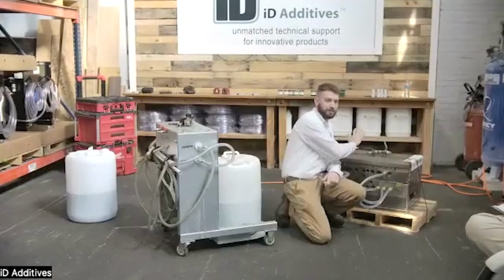Instances where you would need to bypass the filter are in that blockage scenario, right? The filter can act as a blockage just like contaminants in the cooling lines can. So if you've been circulating chemical for an hour or two, and then all of a sudden it stops and you're wondering what's going on, you come over here, you bypass your filter, and if it kicks on, you know that filter's spent because it's collected a lot of contaminants. Just wanted to make quick note of that.